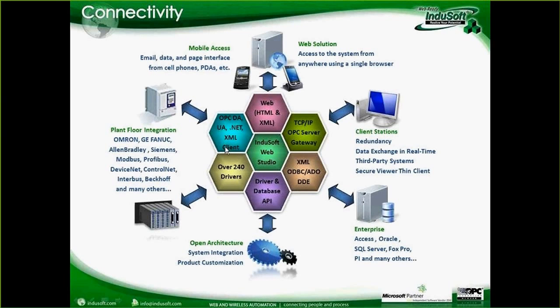Now, those are clients so that we can communicate to anybody else's server and then get to anybody else's device. But we also support OPC Server. We have our own OPC Server built-in, OPC DA Server, HDA, as well as a couple of others, and that allows other OPC clients to come in and communicate with us and get our information out of our tag database within InduSoft Web Studio.